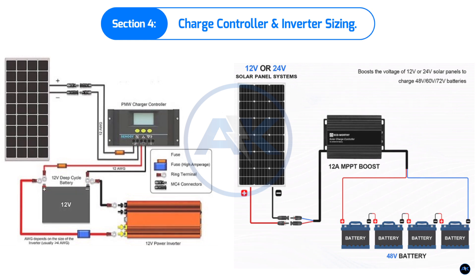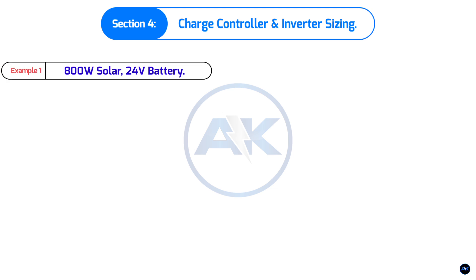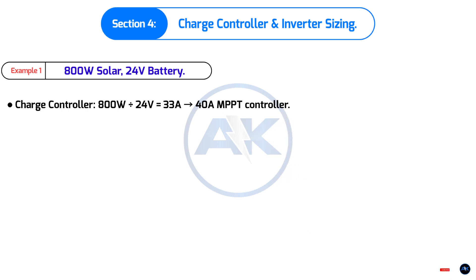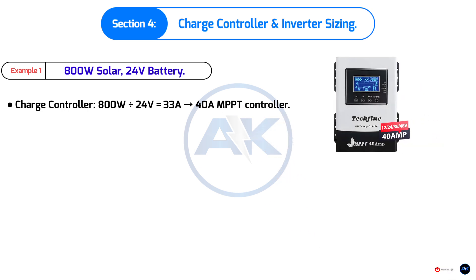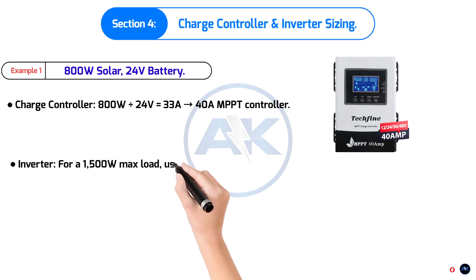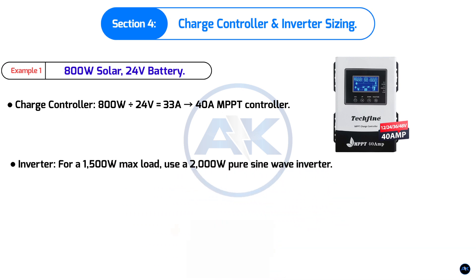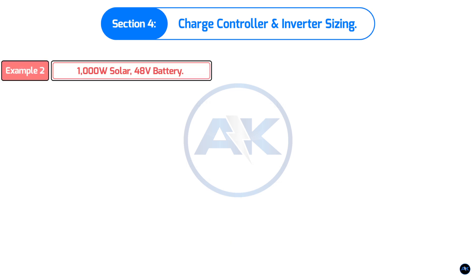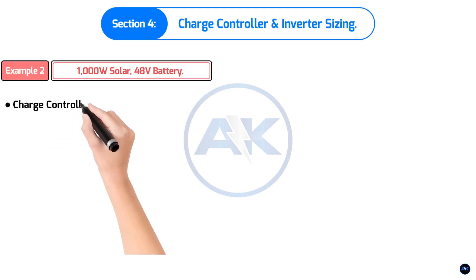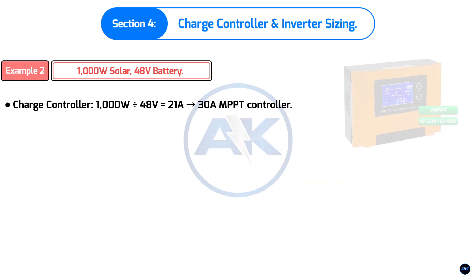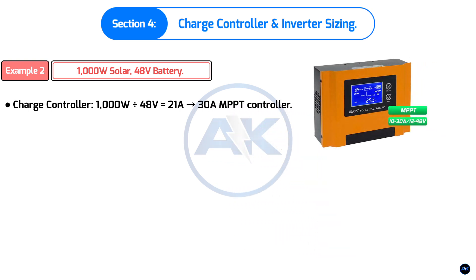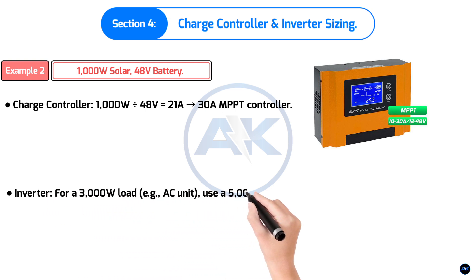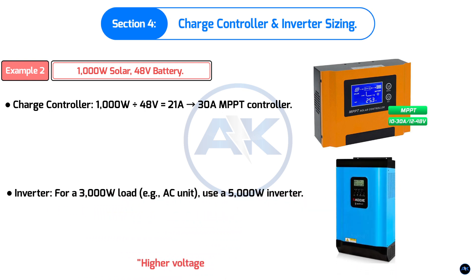Section 4: Charge controller and inverter sizing. Example 1: 800W solar, 24V battery. Charge controller: 800 ÷ 24 = 33 amps — use a 40A MPPT controller. Inverter for 1,500W max load: use a 2,000W pure sine wave inverter. Example 2: 1,000W solar, 48V battery. Charge controller: 1,000 ÷ 48 = 21 amps — use a 30A MPPT controller. Inverter for a 3,000W load (e.g., AC unit): use a 5,000W inverter. Higher voltage (48V) means thinner wires, lower costs, and better efficiency.